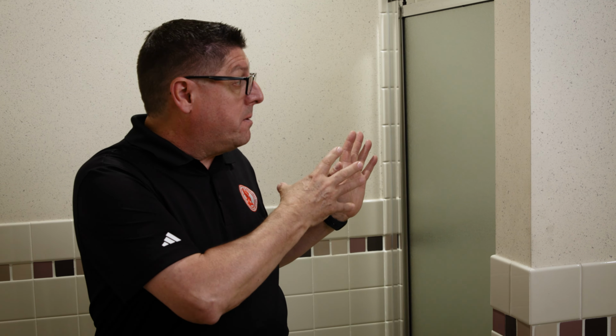The inspection of this particular door: it is a frosted glass, but what I don't have is the tempered etching. I'm simply going to make a remark on my report saying tempered etching is not visible, and I'm going to leave it at that, but I am going to verify that it is all opening outward. Check on the tempered glass etching as well as opening outward on your next inspection as well.